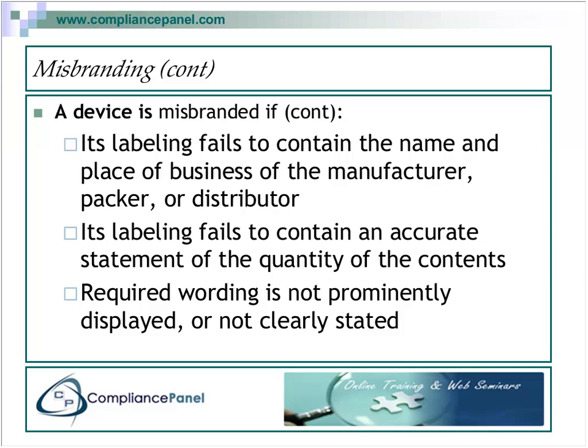Your labeling has to tell how many pieces are in that container. If it's a sterile disposable, it'll be 1. A non-sterile disposable could be a large quantity. Instrumentation, multiples, things like that. You have to have a quantity of the contents on the labeling. A device is misbranded if the required wording is not prominently displayed. It's written in, like, tiny font, for example, or not clearly stated, really vague. As we go on in the presentation, I'll tell you what wording is required depending on the nature of the device.